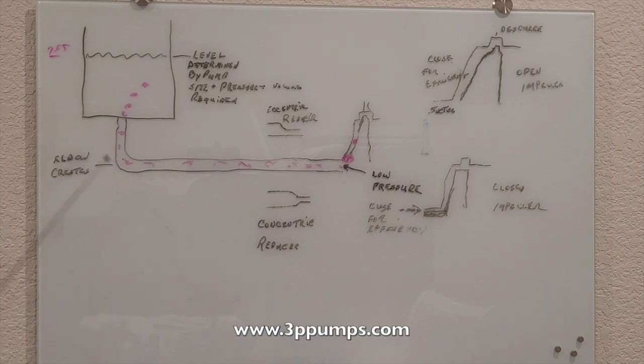Now, cavitation a lot of times is explained by how it sounds. It sounds like marbles running through your pump. And basically what that is, is all these minor explosions in there, and those minor explosions are causing the pump to vibrate, and this low pressure out here also causes a vacuum which tries to pull water through your seal on the other side in your stuffing box over here, and we'll get into that in a minute, okay?